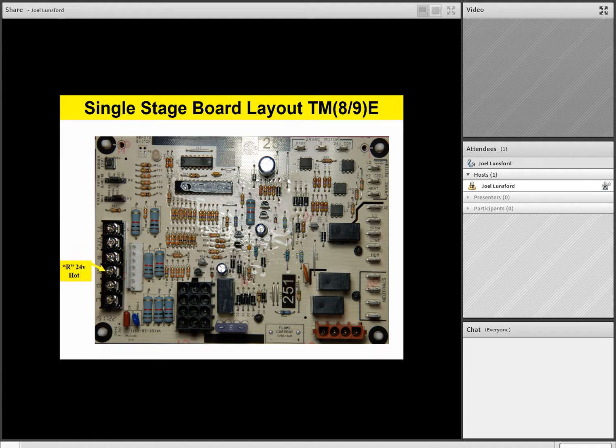W is our heating call from the thermostat to tell the board it's time to go into the heating mode. R is 24 volt hot. That 24 volt hot goes up to the thermostat and powers all the thermostat function, as well as allows the thermostat to switch and to power up the rest of the 24 volt system. So 24 volt hot on the control board is marked with an R terminal.